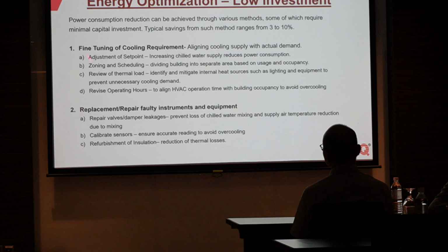One of the things is fine-tuning the cooling requirement, aligning the cooling supply with actual demand. As I mentioned, people wearing jackets in the office is not the right thing. First is adjustment of the set point - what the facility manager or owner can do is increase the chilled water supply temperature to reduce power consumption.